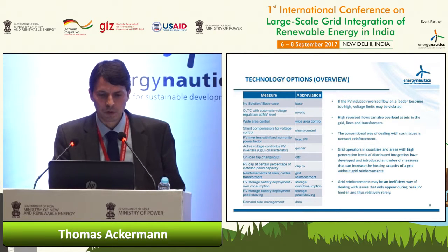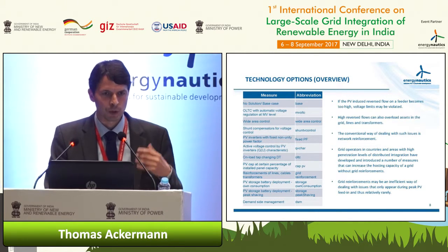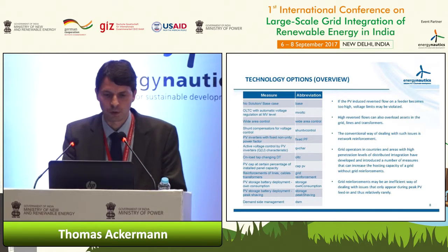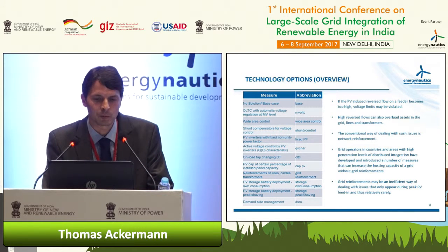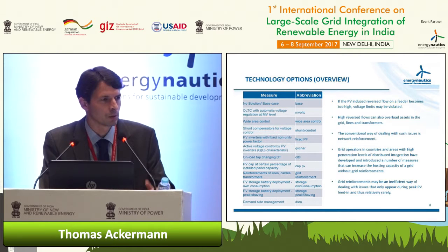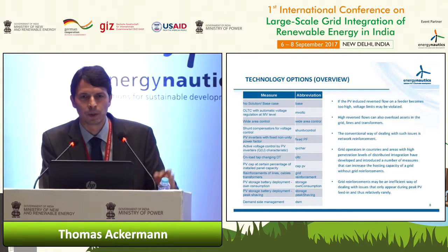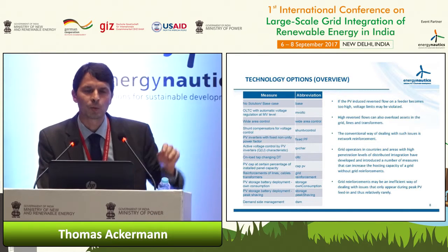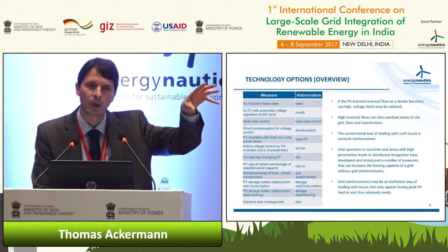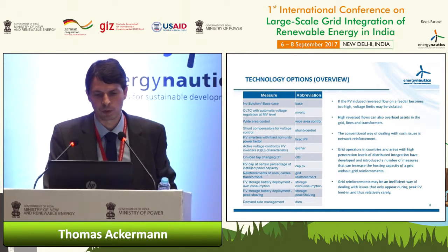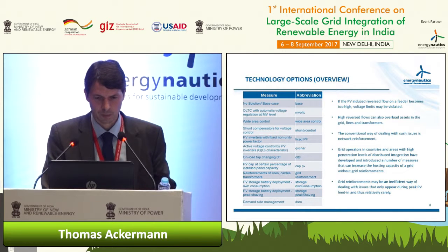Then we looked into various technologies that help with voltage control: on-load tap changing with automatic voltage regulation at the medium voltage level, and wide area control, which is quite common in Germany, where you sense the voltage in the system and set the transformer's tap changer accordingly.